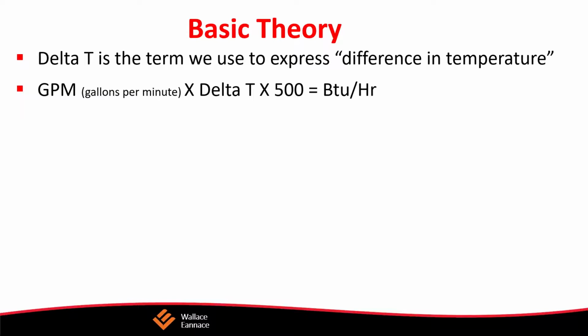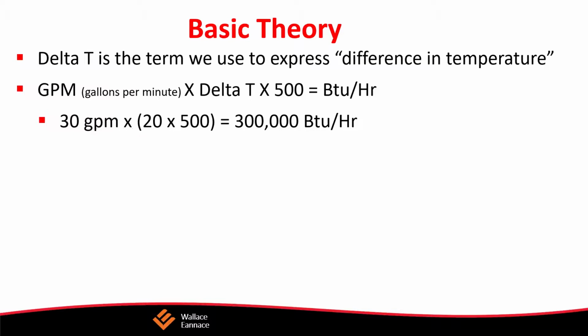When we're designing systems from the outside, we know that the outdoor temperature may go as low in New York, say to 10 degrees, and we may want the occupancy to be 70 degrees. That's a 60-degree delta T. Gallons per minute times delta T times 500 gives me BTUs per hour. So 30 gallons per minute times 20 times 500, which is a 20-degree delta T, will be 300,000 BTUs.